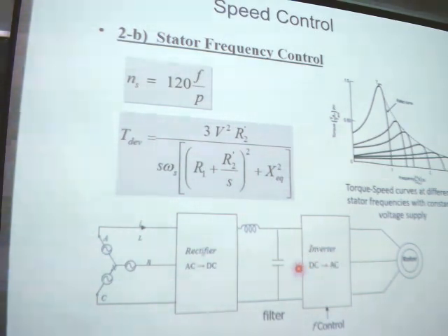It can output zero frequency. It's 0 to sometimes times the rated frequency. It has a wide range. My question is, the rectifier does AC to DC and DC to AC, but our input is AC and output is also AC. So why do we use this rectifier and inverter? The frequency is different. Here it is 60 or 50 hertz, constant. But here the frequency can be changed. Maybe 40, maybe 30, maybe 20, maybe 10. Only for frequency changing, so it can continuously change the frequency.